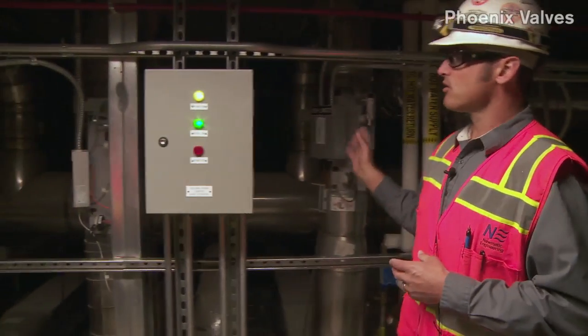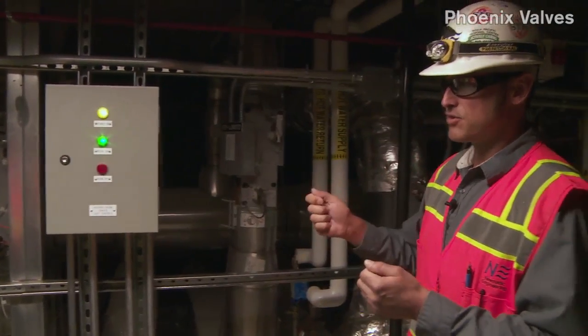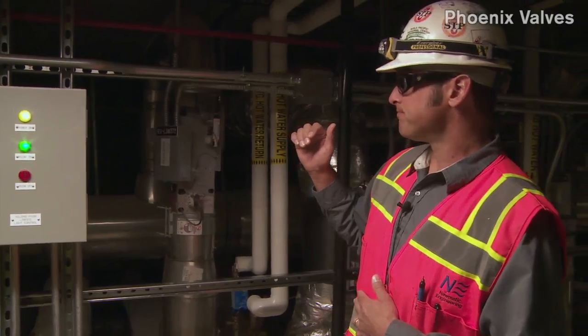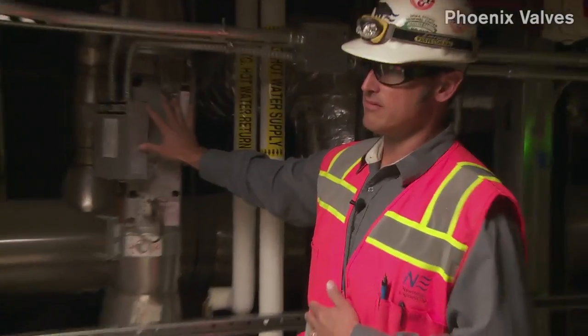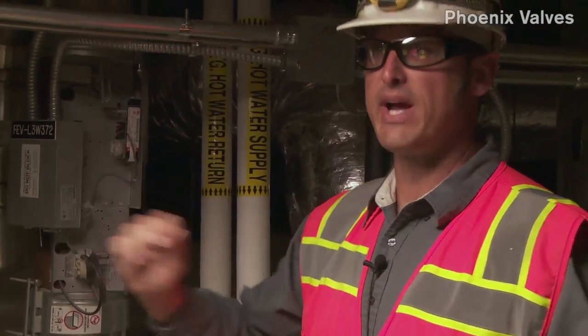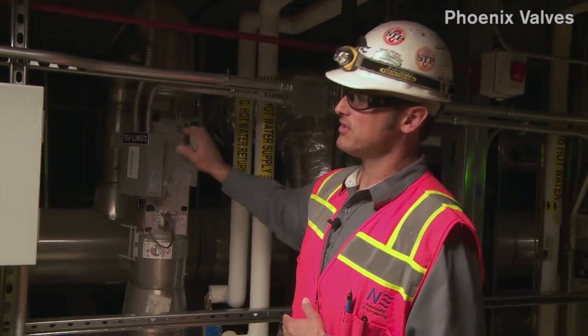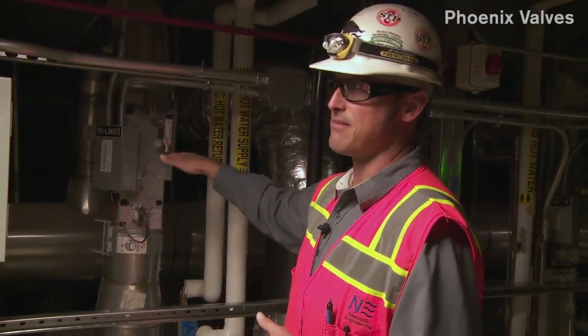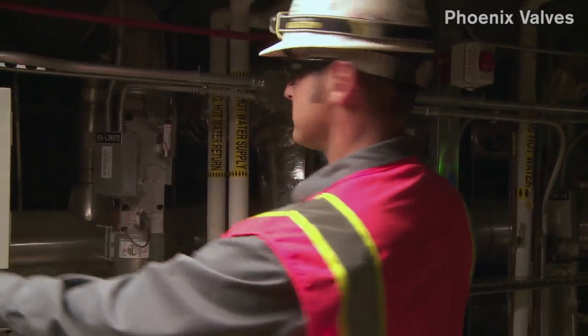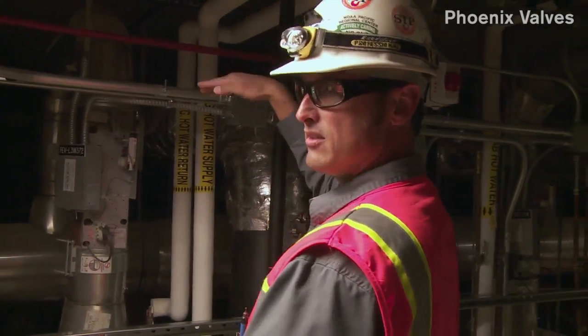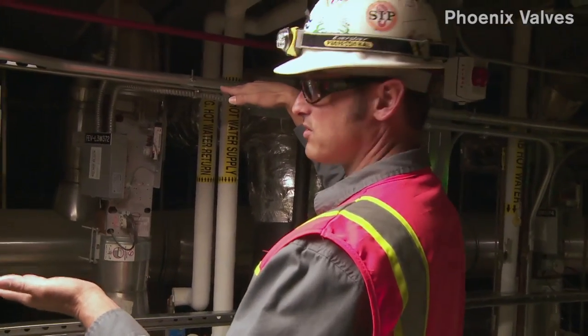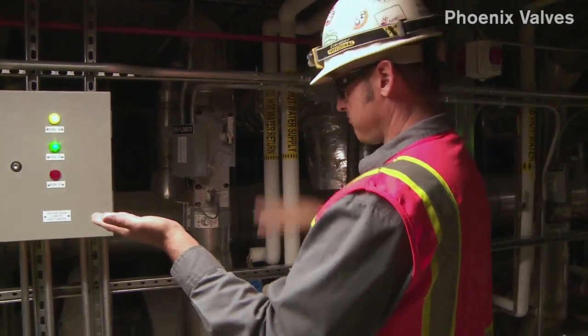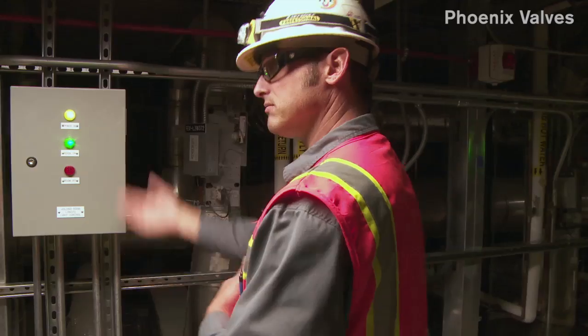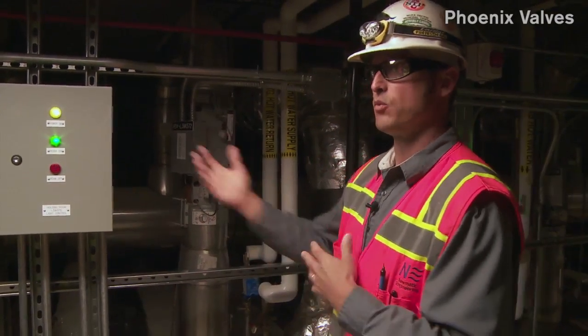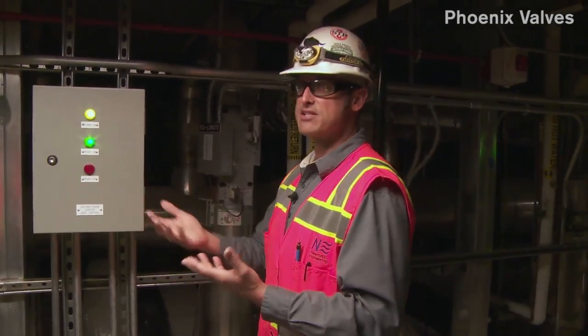These corridors, some of these corridors, are the ones we were talking about that are maintaining the switch through Johnson Controls. When the switch is made from one way or the other, the biosafety hood valves stay constant, because they're actually connected to a biosafety hood cabinet, so that will never change. What's going to make the change is the difference between the supply valve and your general exhaust valve. When we get that signal, we tell the supply valve to go from either 500 supply, 600 exhaust, to maybe keep exhaust the same and make the supply 100 more to make it positive, or negative, vice versa, whatever it is. It's in the startup sheets which way the room goes when it gets the signal, which valve actually moves.